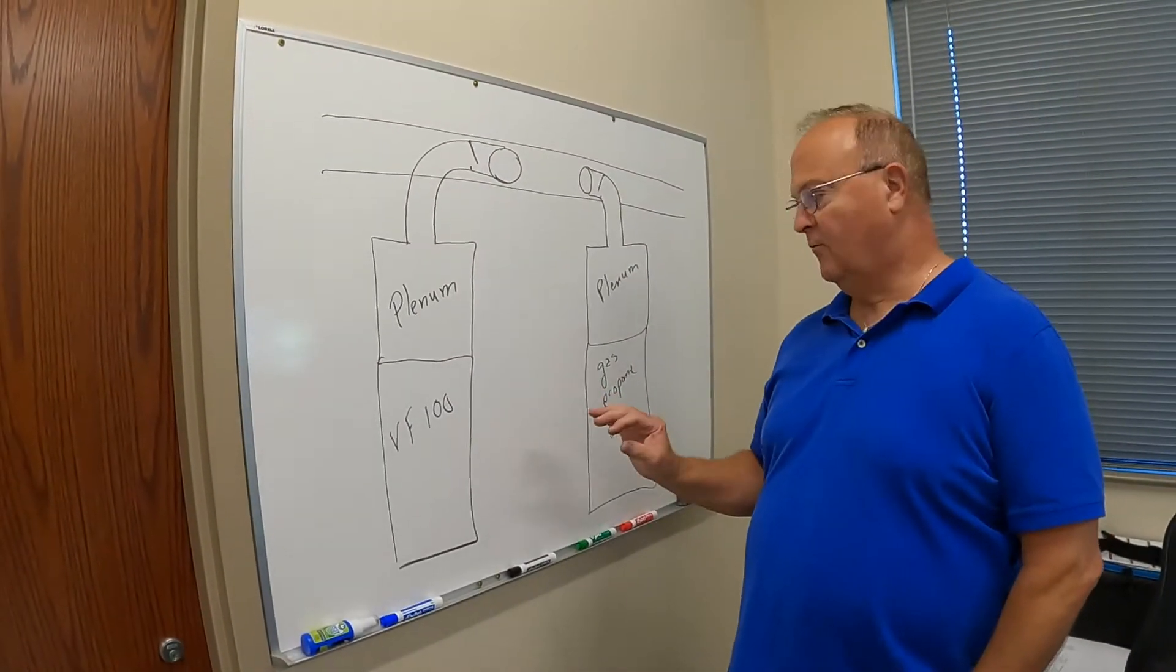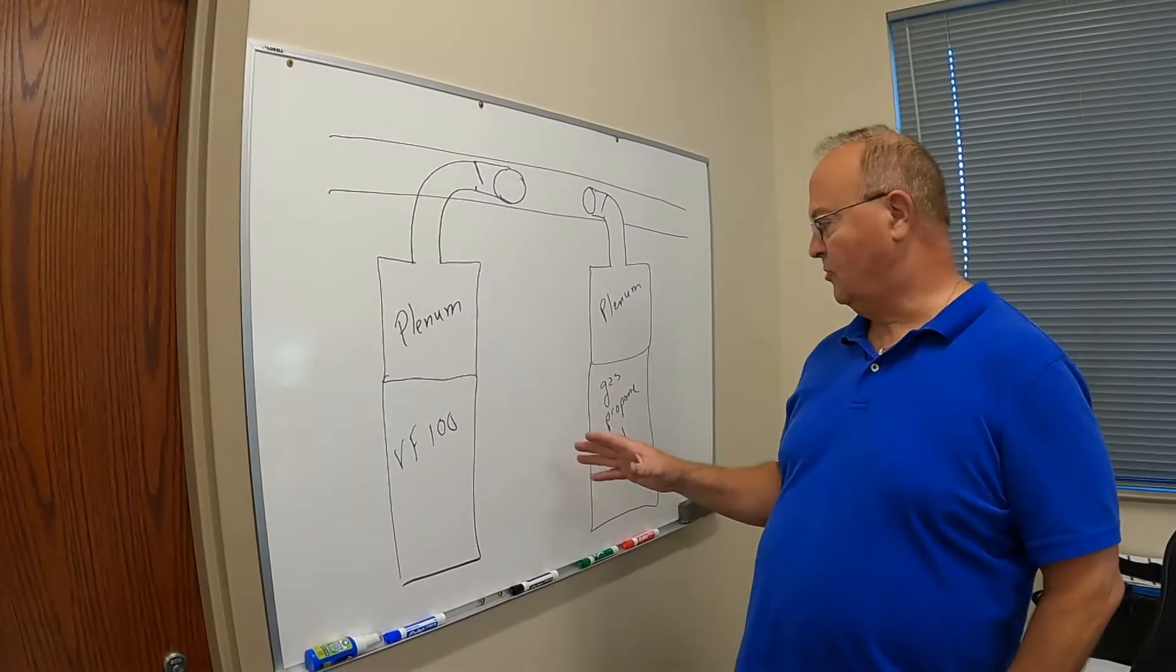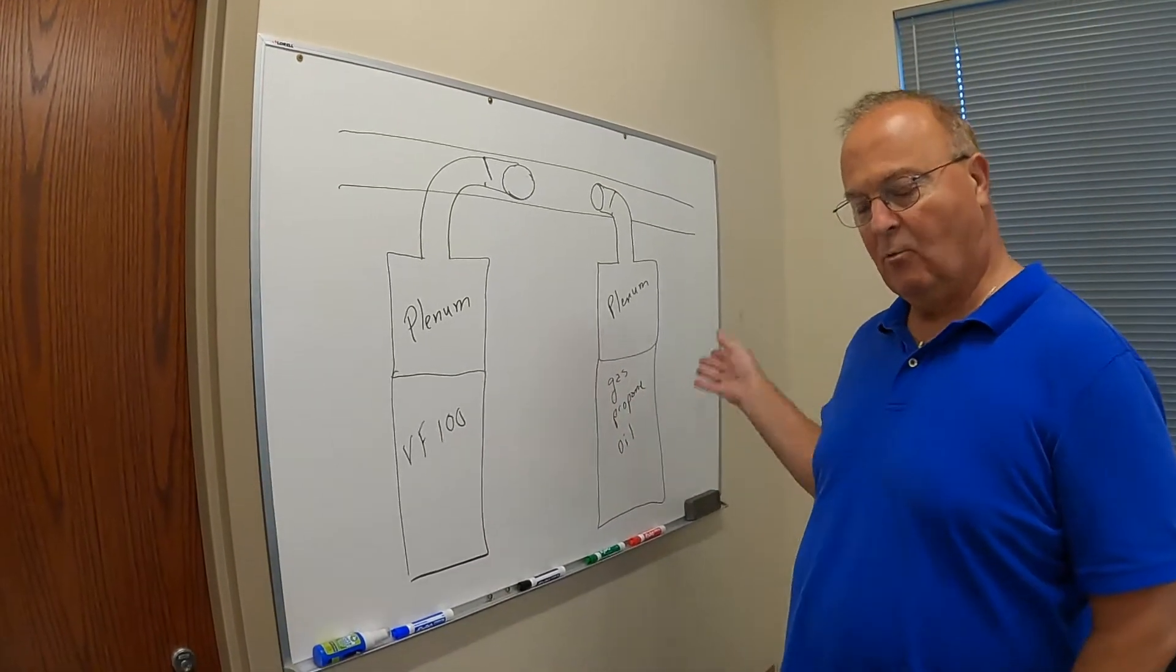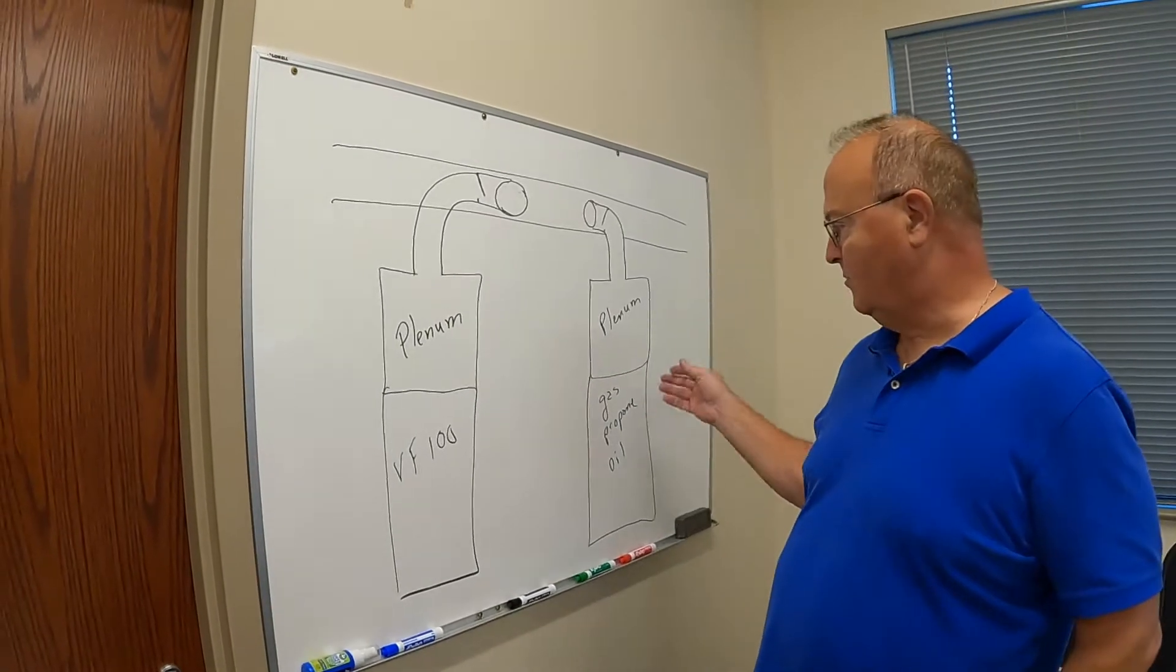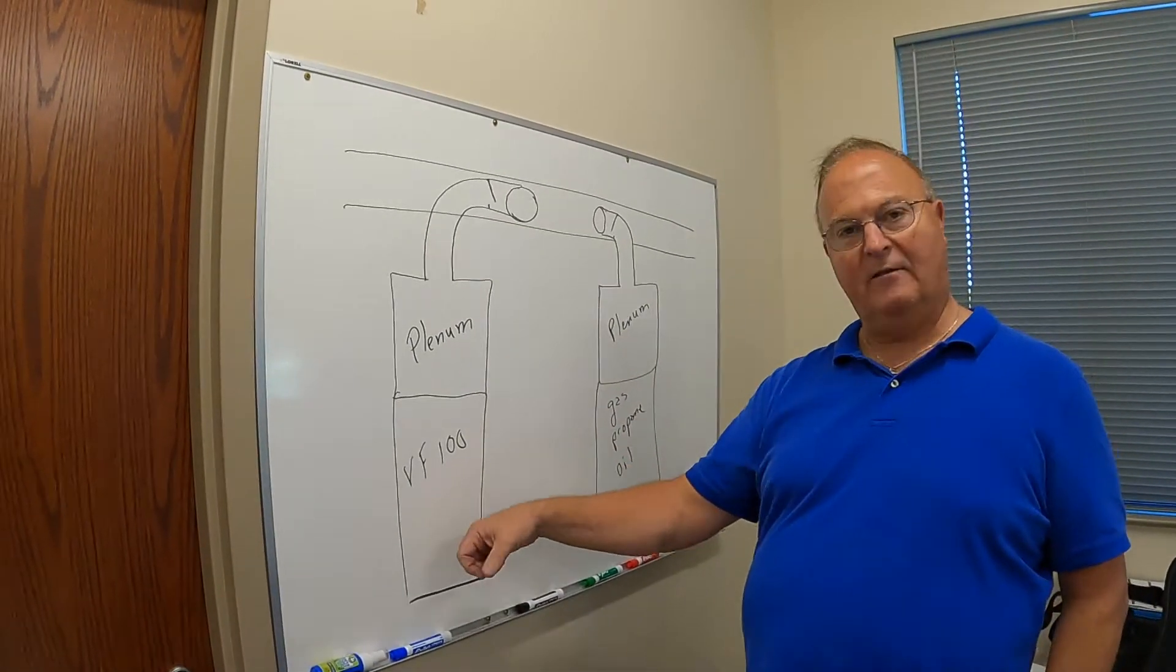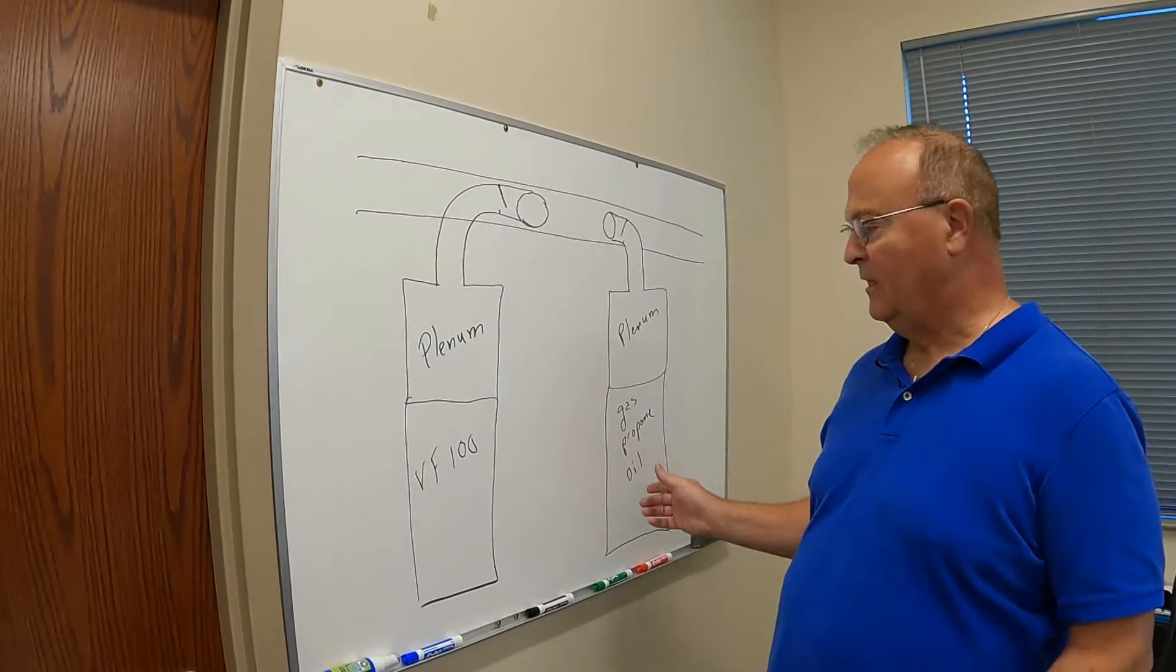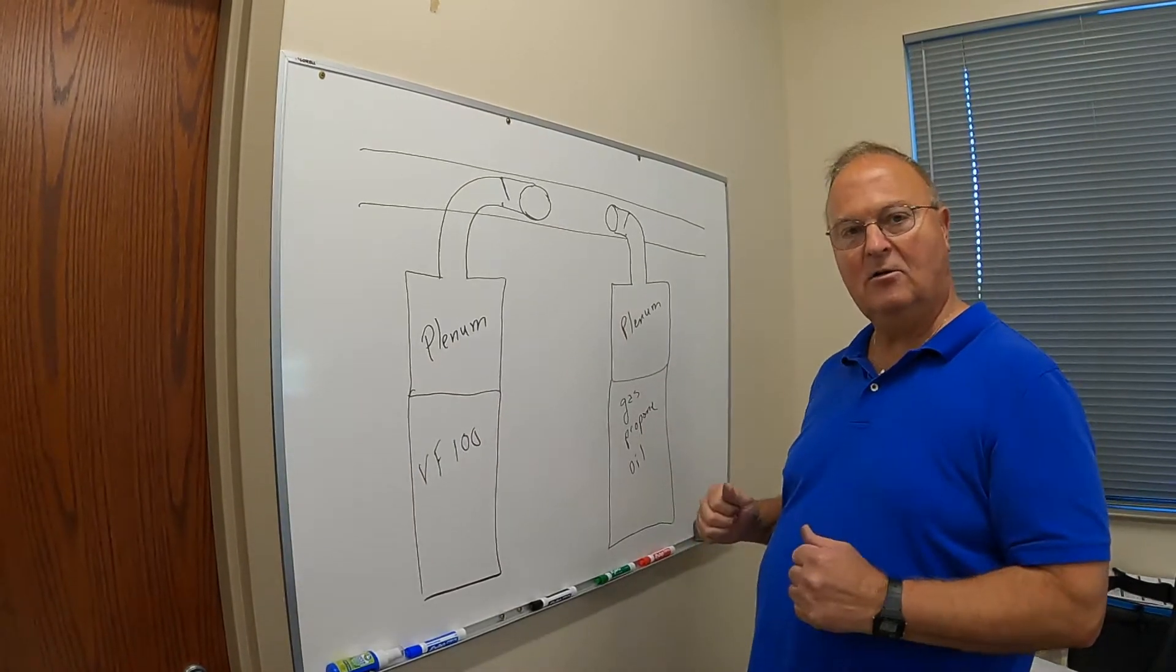So when you're doing the ducting for your furnace, in most applications, you're going to be required to have a backup furnace. Your insurance company is going to want to know if you're in a cold climate like Minnesota or the northern part of the country, that if you're not home and the fire goes out, that you still have backup heat so your water pipes don't freeze. So putting two furnaces in together is called commoning your furnaces.